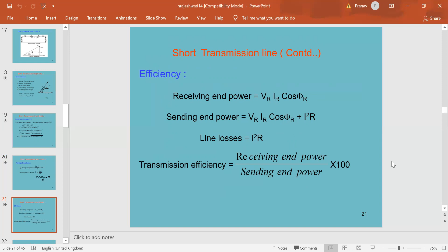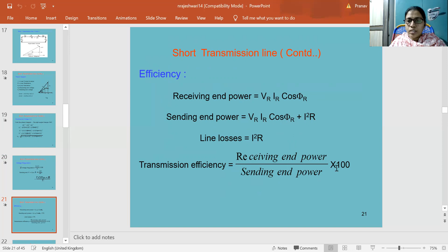And coming to the efficiency of the transmission line, the receiving end power is equal to VR IR cos phi r, and the sending end power is equal to VR IR cos phi r plus I square R. The line losses will be I square R. So the transmission efficiency is equal to receiving end power divided by sending end power into 100. By substituting these, we'll get the transmission efficiency.